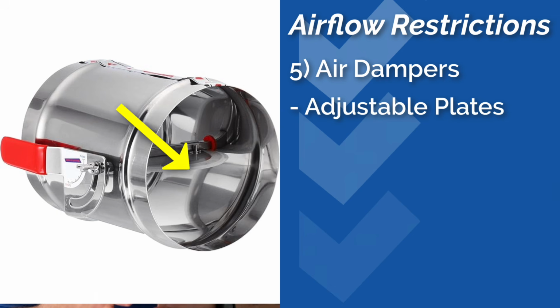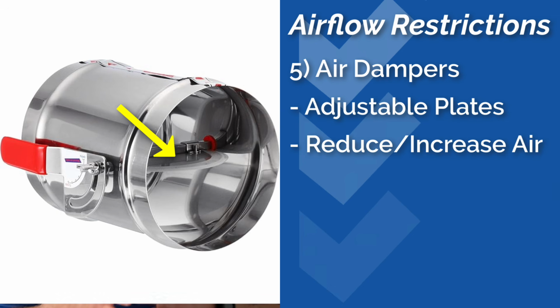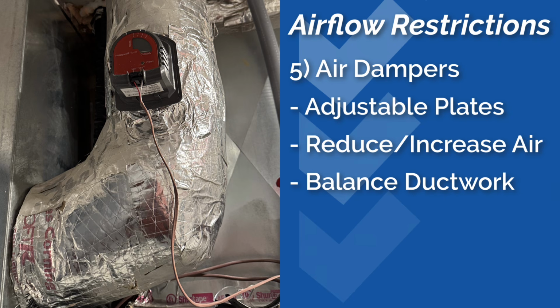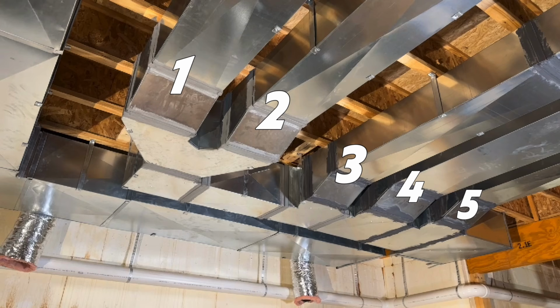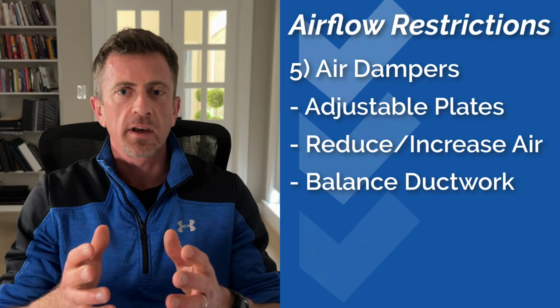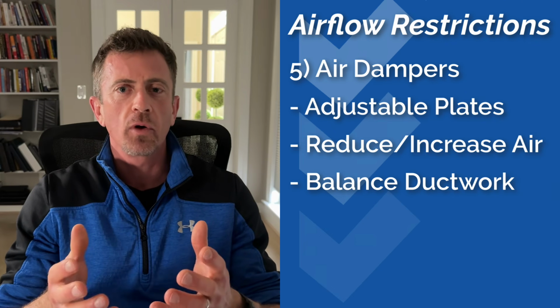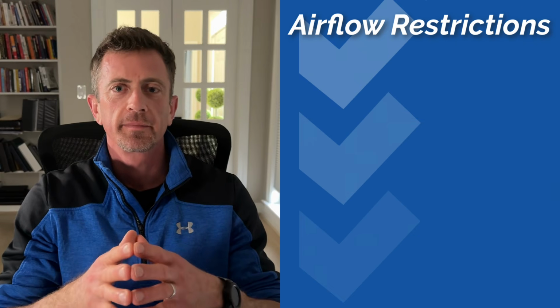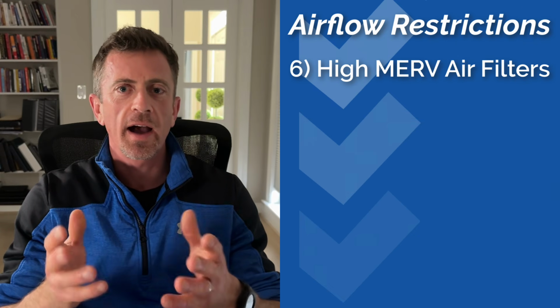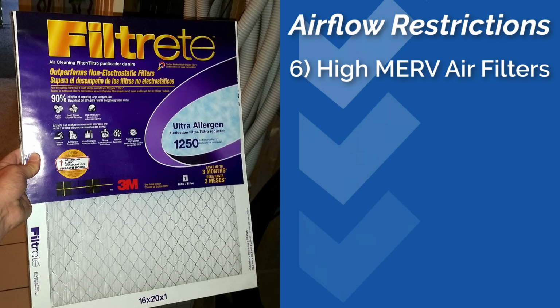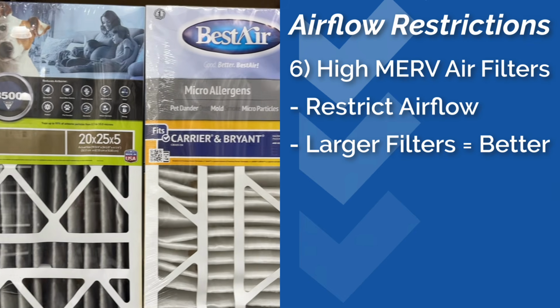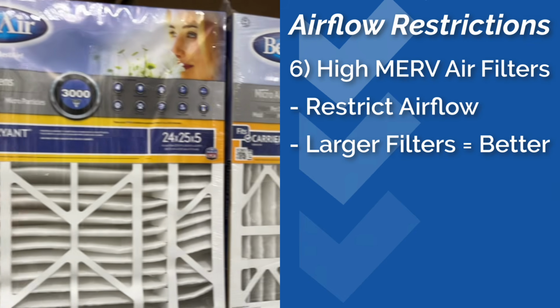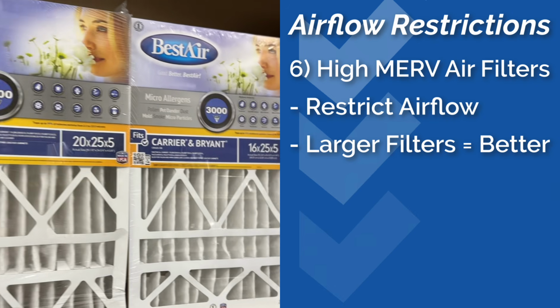Next restriction up are dampers. These are the adjustable plates inside ducts used in zone systems to reduce airflow and balance ductwork. They're also found in non-zone systems as well, but usually you find these in zone systems in new construction. If they're not set right or they get stuck, they'll block a lot of airflow, and they'll have to be opened back up manually if they're not automatic. The last restriction we'll talk about are high MERV air filters. Like we just discussed in Chapter 7, high MERV filters can restrict airflow if they're too dense or too restrictive for your system. Make sure you pick the right size filter for your equipment and something that's not too restrictive that's going to cause a problem down the road.